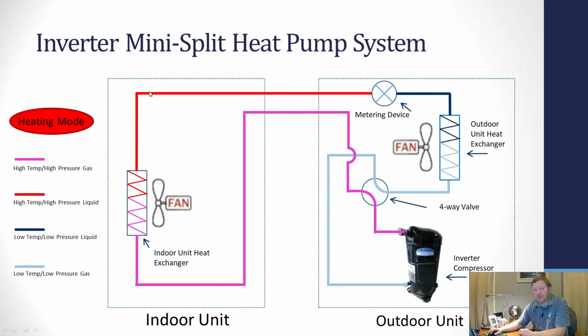That liquid then goes back to the outdoor unit and then through what's called an electronic expansion valve. And we talked about this component in the last video. This is a big difference between traditional heat pumps and inverter heat pumps. When you have a compressor that is adjusting its speed according to the demand in the space, which we'll talk about shortly, you also need an expansion valve that can adjust its position relative to the compressor. So as we discussed, that metering device is what is getting you that pressure drop. So that high pressure, high temperature liquid is then going to become a low pressure, low temperature liquid.